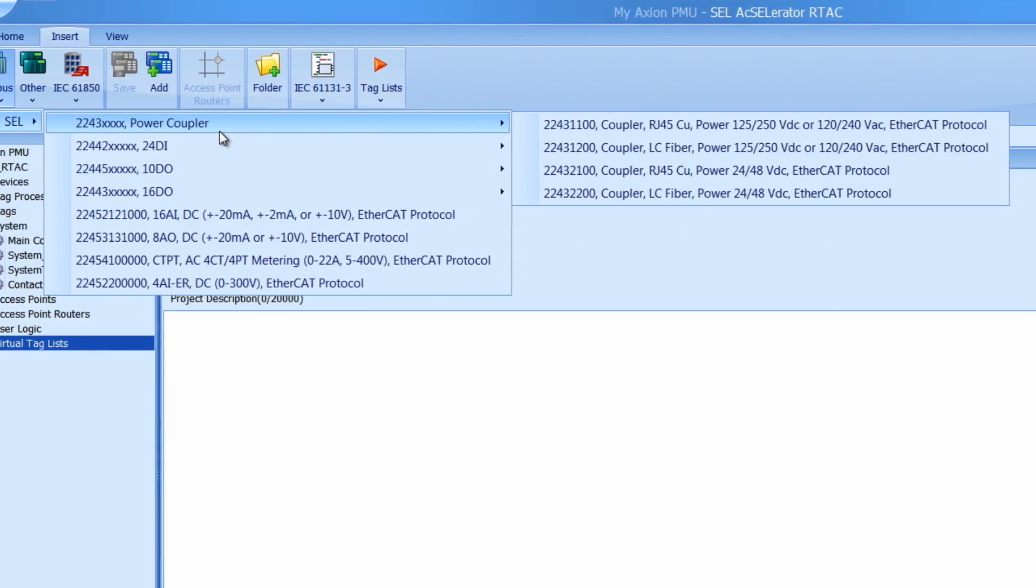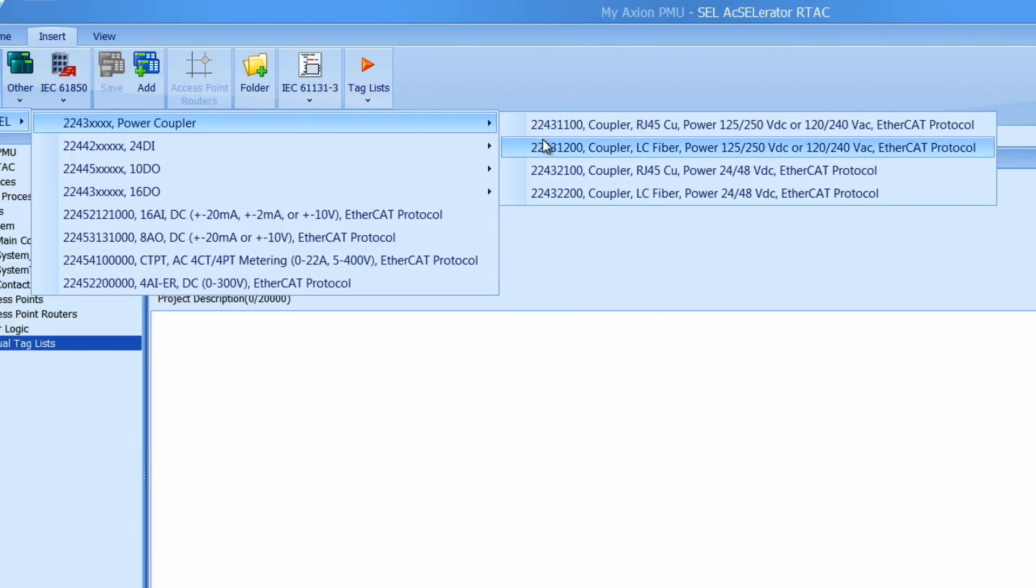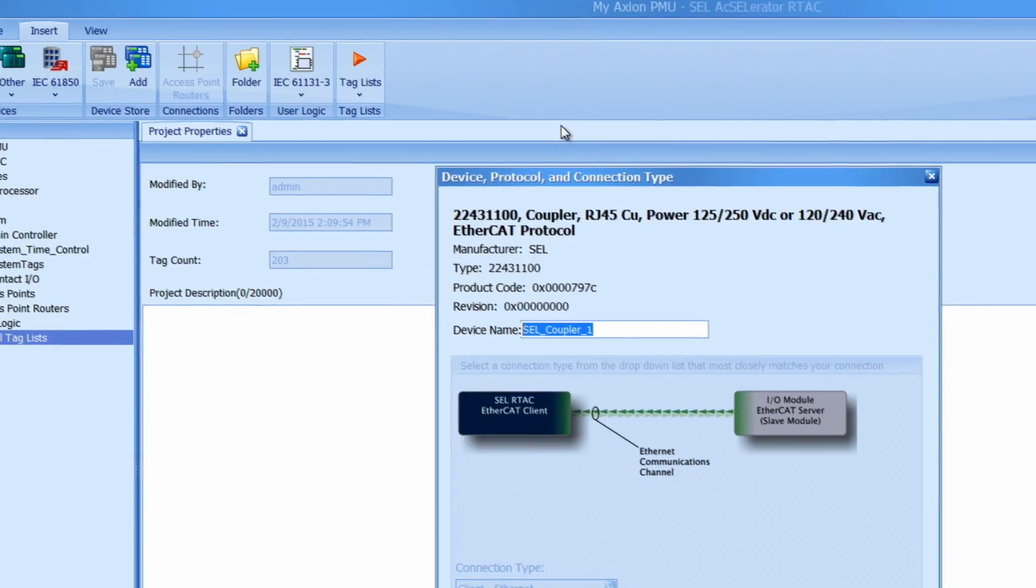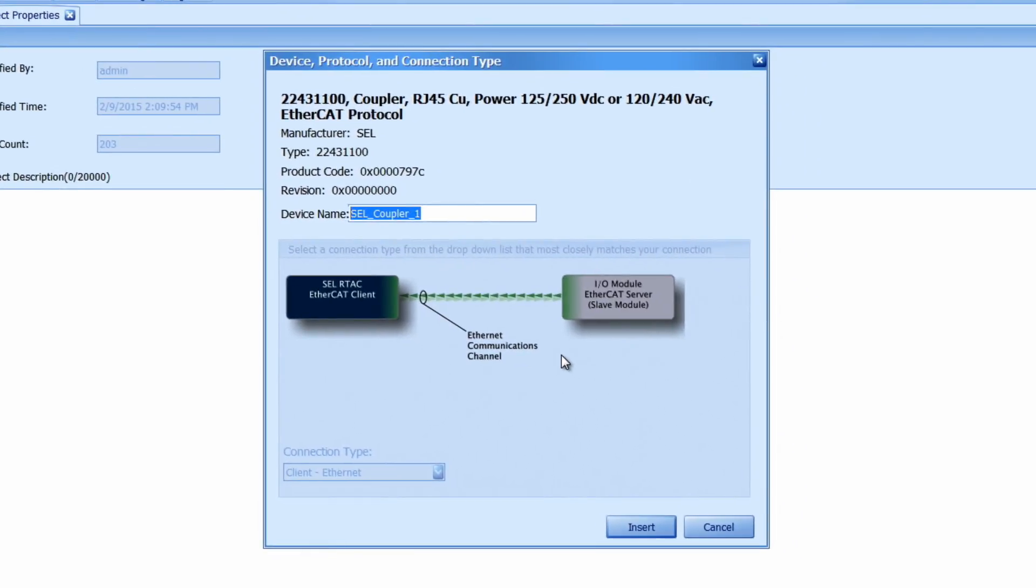The first one I want to add is the power coupler. I'm going to select the first one on this list because I'm using a copper power coupler with 125 volt DC input and give the power coupler a helpful name. In this case I will call it power coupler or PC underscore slot B because my power coupler is in slot B.